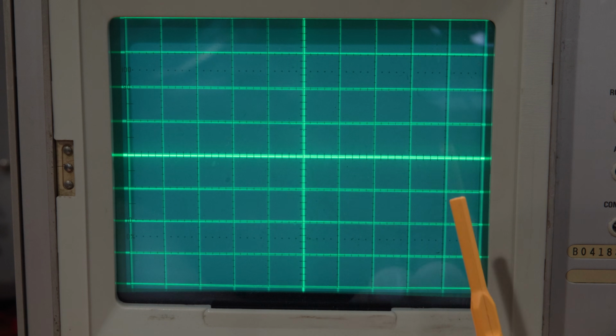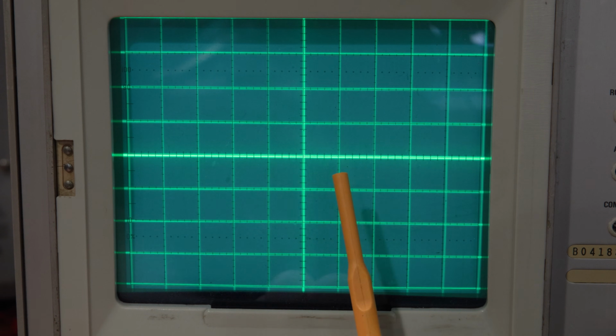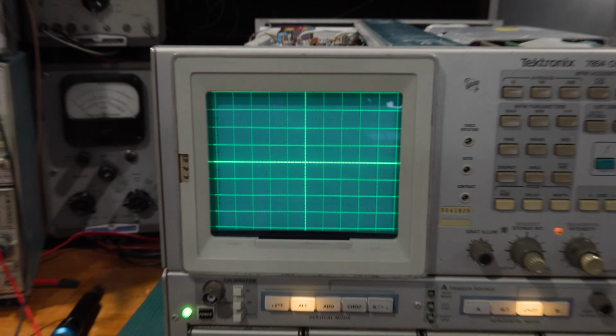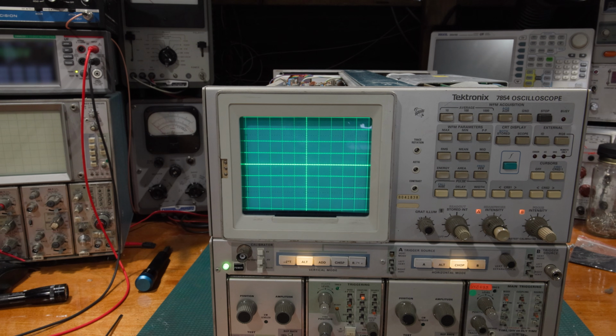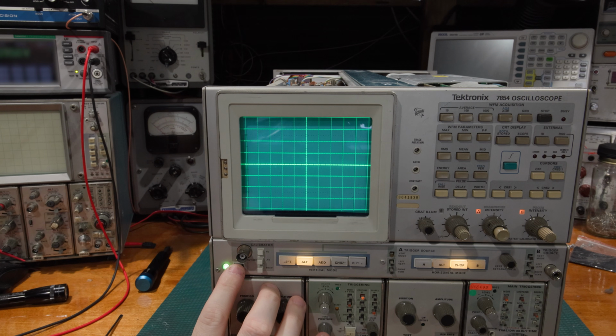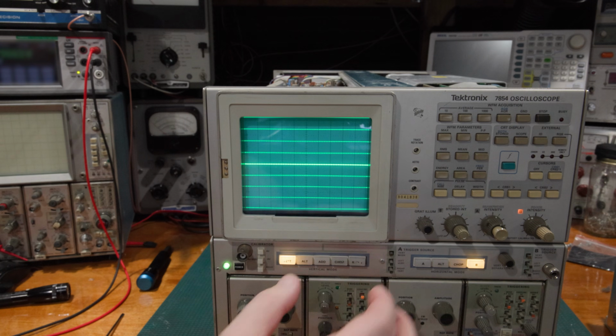I also have some sweep linearity problems where the sweep is good and then it starts deviating, as these lines should be lined up. And so I have sweep linearity problems. Now, sweep linearity is actually adjusted in two places. One, it's adjusted in the time bases themselves, and it's also adjusted in the frame. So I checked. I've calibrated this time base personally here in the lab. I have not calibrated this time base, and I have not calibrated this 7B87 that we were using before. And why is this so important? Well, let's switch out to the 7B87. Alt and chop.